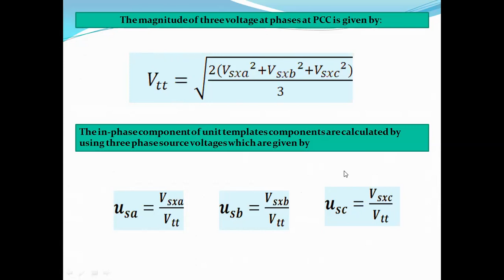Similarly, now for synchronous reference frame theory, we have to generate three unit vectors for the calculation of harmonic content, and to eliminate it by using these vector elements such as USA. USA can be determined by taking the source voltage for A phase divided by this PCC voltage. Similarly for B phase, the voltage for B phase divided by this PCC voltage. This PCC voltage is common for all the unit vectors. So we have to generate these unit vectors to remove the harmonics by using SRF theory.